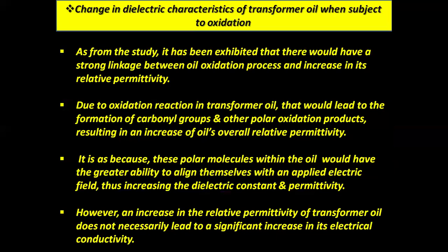Let's start with the change in dielectric characteristics of transformer oil when subject to oxidation. From the study, it has been shown that there is a strong linkage between the oil oxidation process and an increase in its relative permittivity.